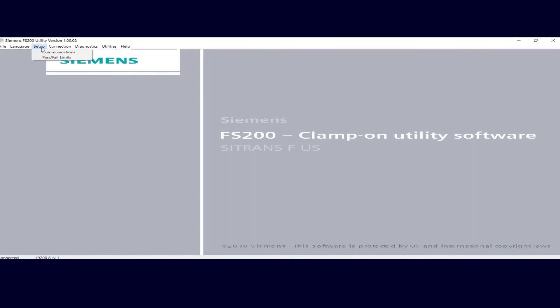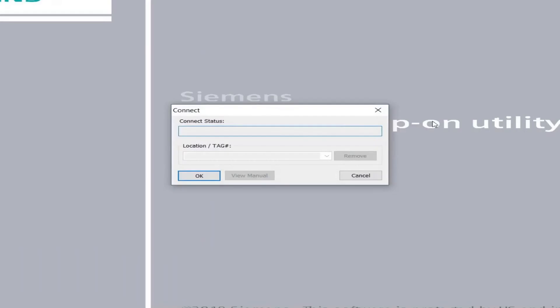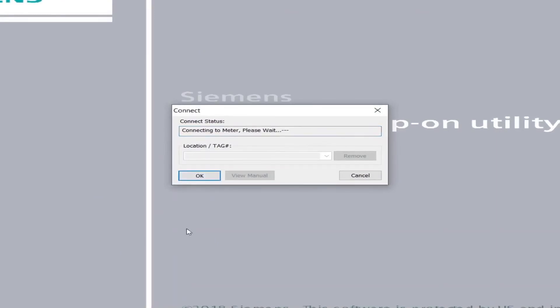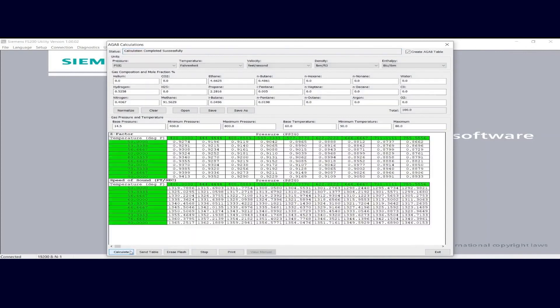Click the Setup tab and click Communications Connections. Be sure that your device address is 1 — if there's no device address, the FS-200 utility won't be able to communicate with your flow meter. Make sure your baud rate is at 19.2 and that it's connected to the correct COM port, then click OK. Come to the Connections tab, click it, then click Connect. A dialog box will open showing the connection status — click OK to initiate communications. Once that box goes away, you've established communication with your FS-230. Now go back to your Utilities tab, click the AGA-8 Calculation button, click Calculate, and you'll be right back to your AGA-8 table. Come down and click the Erase Flash button to erase the existing AGA-8 table in the FS-230 flow meter.